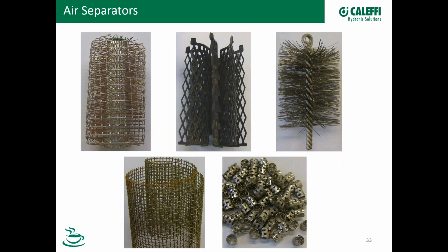In this testing we did, we compared a lot of different products on the market, and here are some images of the 5 brands that we tested. It really comes down to this: all the popular air separators that are available and successful on the market have some type of coalescing media that you can see here. They all allow bubbles to cling to the edges of that media, and over time and over a number of passes, that air is removed. Depending on the coalescing element, some may be faster than others. Some may stand up to chemicals and impurities better than others. That top one in the center is ours. It's a type of non-metallic product, and that really holds up to chemicals if there are chemicals in the water.